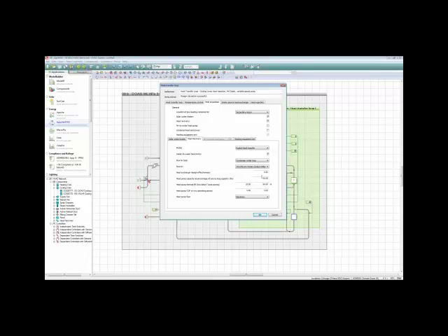And again, I have the choice of whether or not I want to add this water-to-water heat pump to upgrade the heat. Say my condenser water loop is 80 degrees, and I want to be putting 120 degree heat on this loop, especially if it's a hot water loop. I'm going to want that heat transfer loop. I might be more likely to get away with just a heat exchanger.